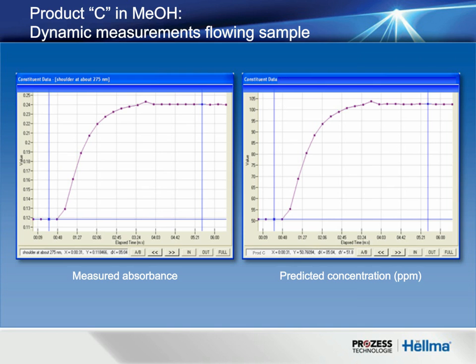Do you have to identify all the potential components of the rinsate? No, not necessarily. From a broad-scale application, because the solvent is typically UV transparent, having some UV absorption is indicative of having some cleaning process still occurring. Ideally, yes, it would be nice to characterize the spectral absorbance of each component, but typically you would qualify this around the most dangerous product, which would carry the highest risk of being carried forward into subsequent batches.